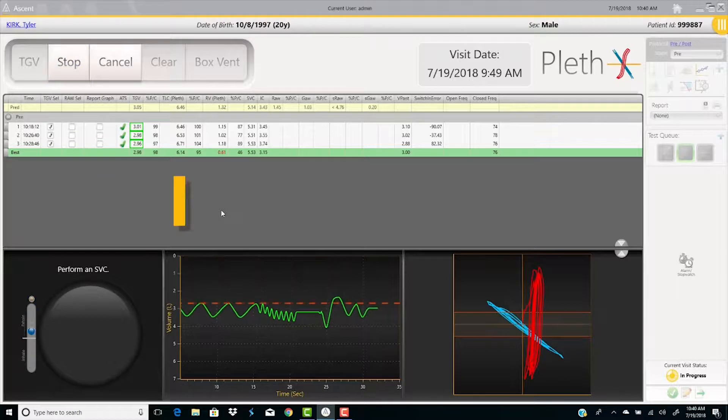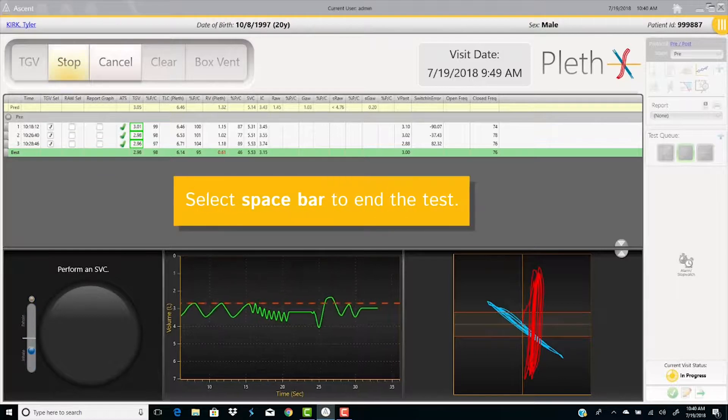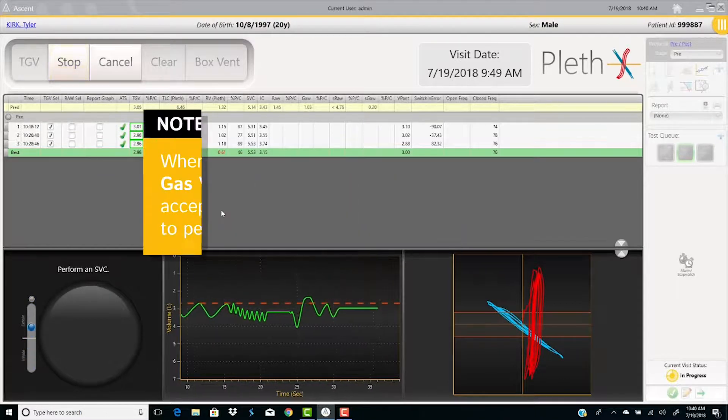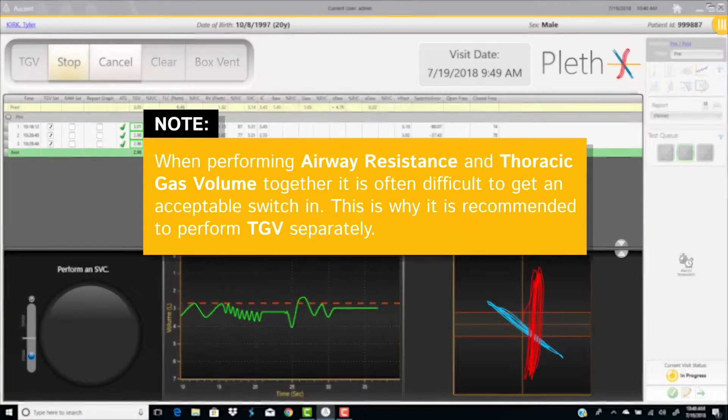Select the space bar to end test. Note, when performing airways resistance and thoracic gas volume together, it is often difficult to get an acceptable switch in. This is why it is recommended to perform TGV separately.